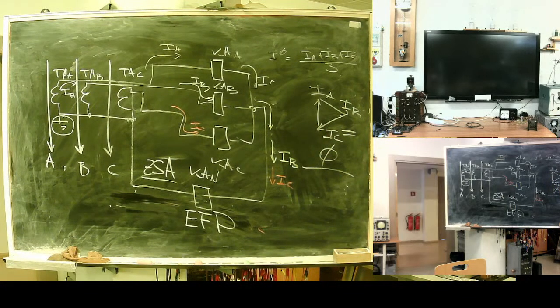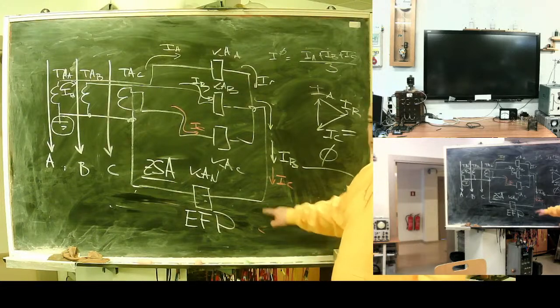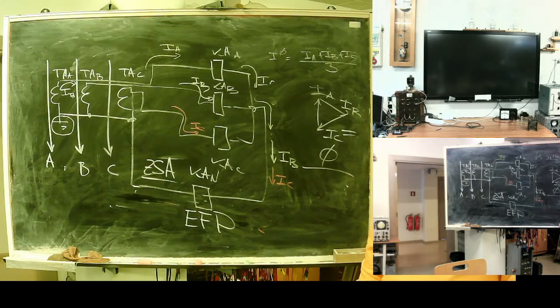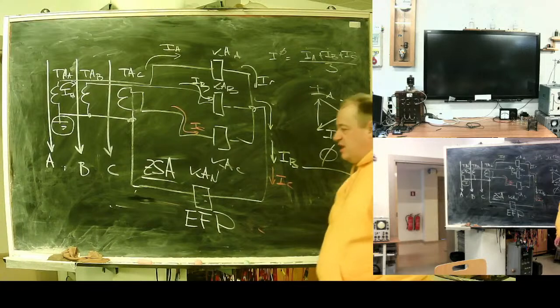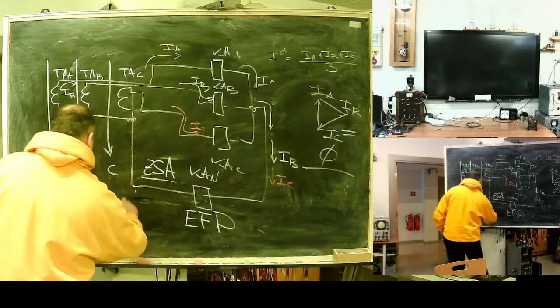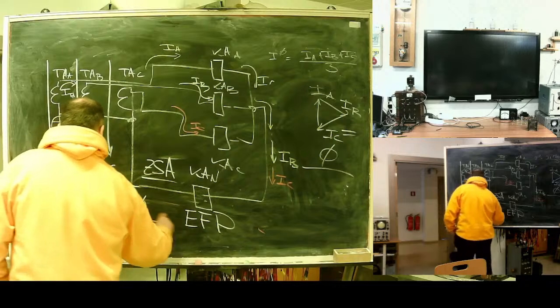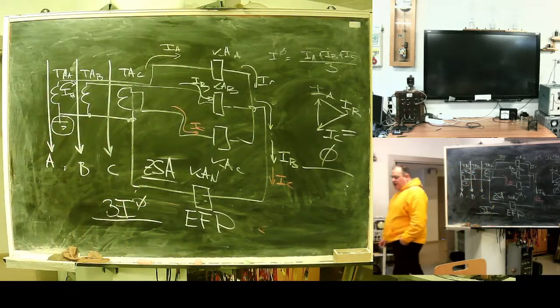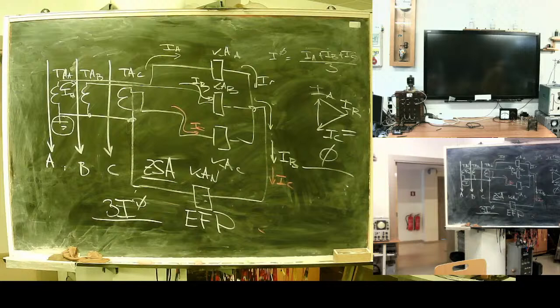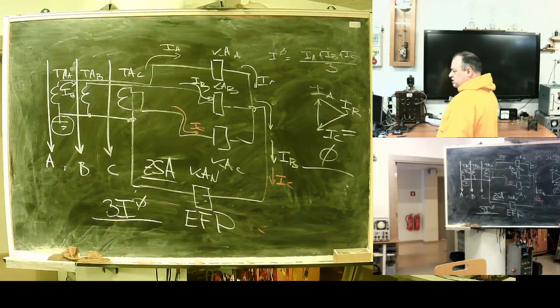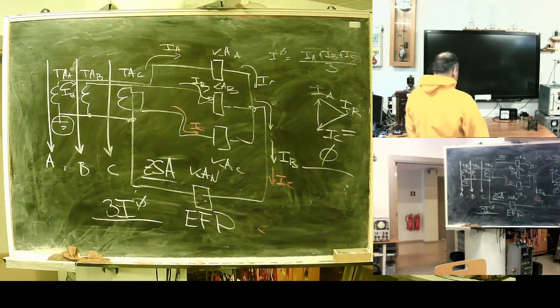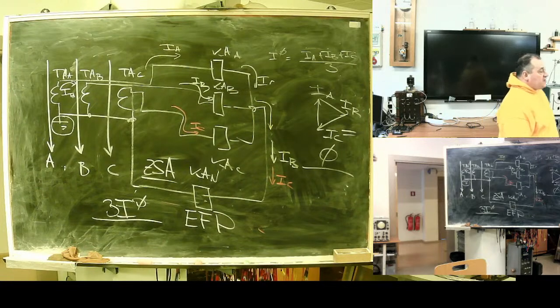Current in the ground wire of full star at the first glance is a zero sequence current. Only triple zero sequence current, triple I0. Very good for earth fault protection at the first approach. For network which effectively earthed neutral, it's true.